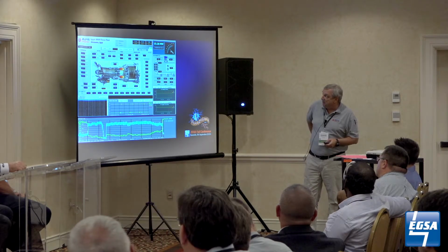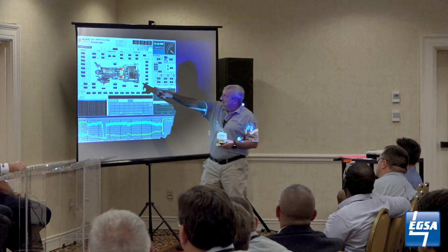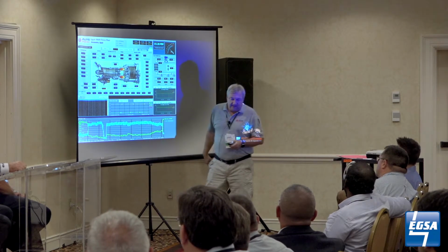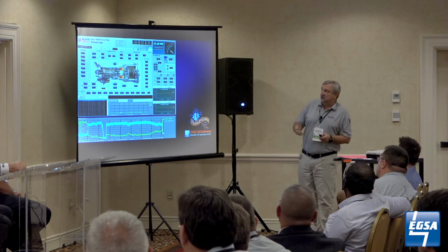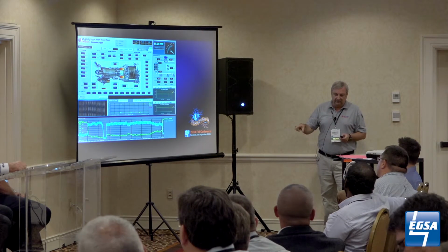There's other diagrams that we also look after. This is what we call an annular combustor system. So we're looking at temperature probes all the way around the gas turbine and making sure that all the fuel nozzles are injecting the fuel and the water correctly into the combustion system, and that we've got an even flame front around the whole annular combustor to make sure that we're burning correctly and we don't have any issues internally.